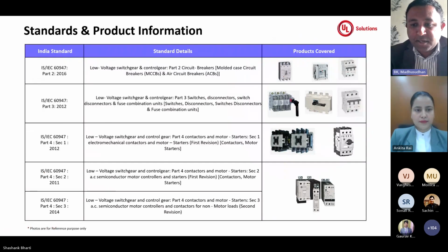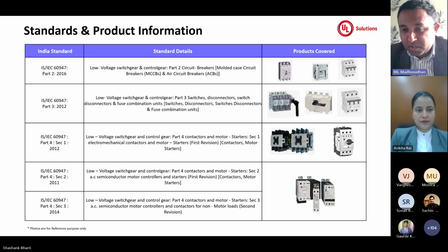Yeah, so as said, as per QCO, the guidelines for the 60947 series, the complete product standard is available for getting the product certified. Basically, the 60947 part 2 category covers molded case circuit breakers and air circuit breakers. Part 3 covers switches, disconnectors and switch fuse units. Part 4 section 1 covers contactors and motor controllers. Part 4 section 2 covers semiconductor controllers and starters, whereas part 4 section 3 covers semiconductor motor controllers and contactors for non-motor applications.